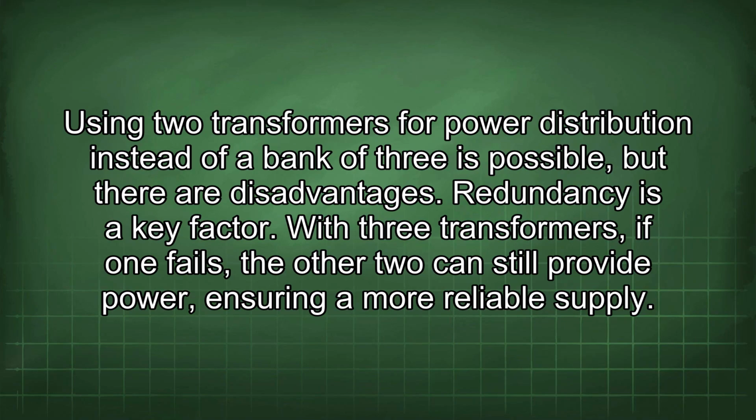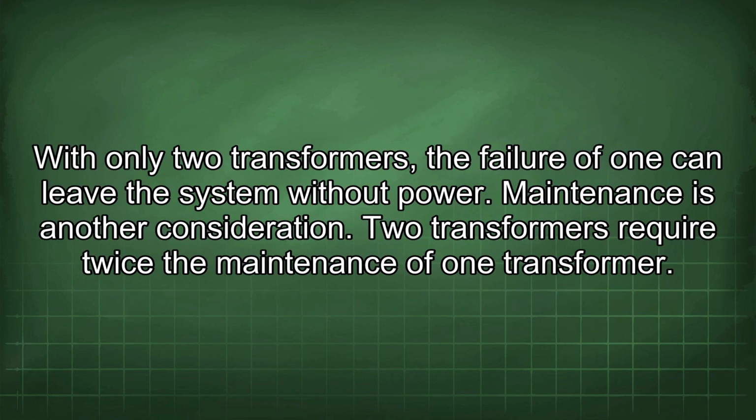Using two transformers for power distribution instead of a bank of three is possible, but there are disadvantages. Redundancy is a key factor. With three transformers, if one fails, the other two can still provide power, ensuring a more reliable supply. With only two transformers, the failure of one can leave the system without power.